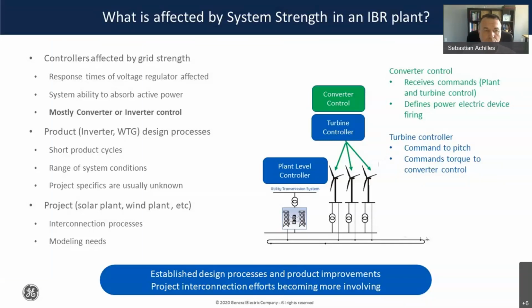Now, how does a vendor come up with the settings and configuration for a converter control? If we know we can have a weak grid, why isn't it just already configured for a weak grid, and we're done with this problem? When you look at design processes for converter controls in wind turbines, or inverter controls in PV as they are typically called, you see a number of things. One is that these are short product cycles, so a product is good for one, two, three years. Maybe one is too short. Let's say two, three years. So in two, three years you're going to be doing a new product. You cannot be designing this product for ten years because the product is going to be good for three.